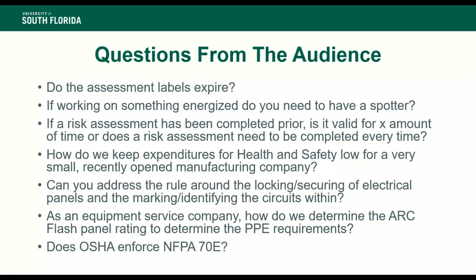Our next question. Does OSHA enforce NFPA 70E? I'll take that one too. It's simple. No. OSHA does not enforce NFPA 70E. They do, however, as I said earlier in the presentation, use NFPA 70E to back up their issuance of a general duty clause violation, because they can link the violation to a recognized hazard under NFPA 70E.